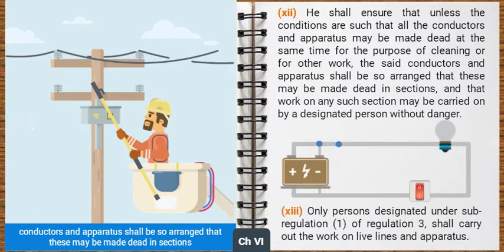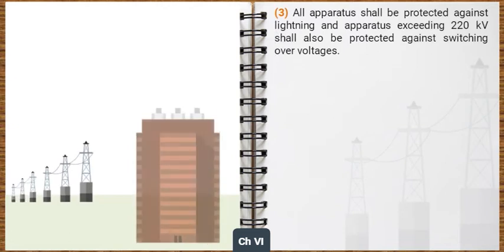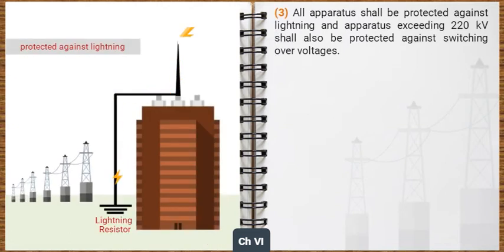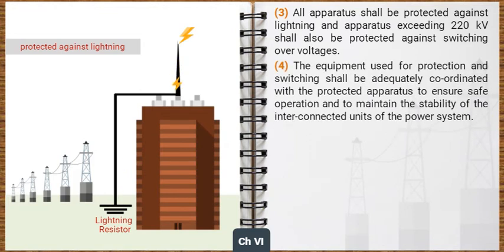Only persons designated under Sub-Regulation 1 of Regulation 3 shall carry out the work on live lines and apparatus. All apparatus shall be protected against lightning, and apparatus exceeding 220 kV shall also be protected against switching over voltages. The equipment used for protection and switching shall be adequately coordinated with the protected apparatus to ensure safe operation and to maintain the stability of the interconnected units of the power system.